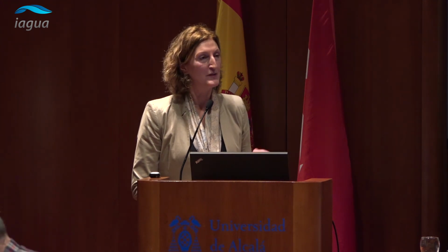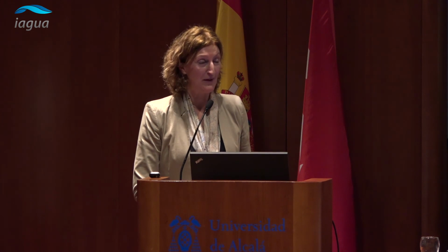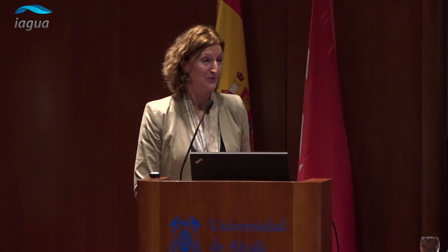I should also maybe tell you at this stage that you can also measure biopolymers, so that's another surrogate parameter, but measuring TEPs continuously is very difficult. And if the algal bloom is very severe, the concentrations change very quickly. But it is a good idea maybe to get a baseline for what it is like when you don't have a bloom, and then how high it can be in a bloom. So it is good to get at least some actual data, but there's no online device, no. I know Kurita in Japan were working on one at one stage, but I think they gave up. I never saw the device appear on the market, so I'm not very hopeful that they actually managed to produce it.